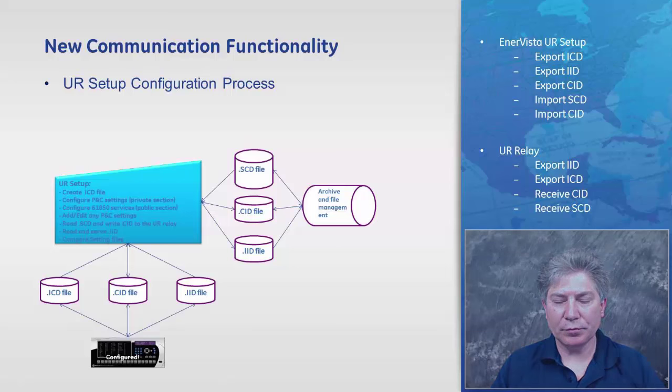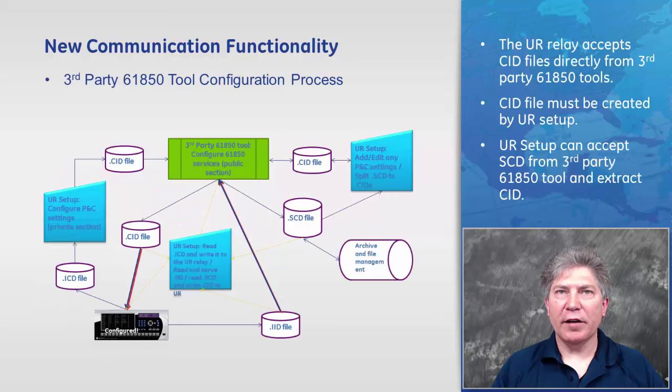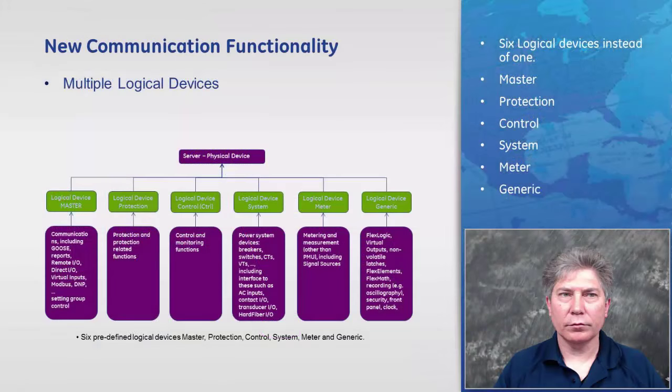It still maintains the original functionality of configuring and editing P&C settings and configuring and editing 61850 services. The UR relay will accept CID files directly from third-party 61850 configuration tools if the original CID file was created from the UR ICD file. The UR setup program can import an SCD file from a third-party 61850 configuration tool and strip off the UR portion and write the CID file into the relay.